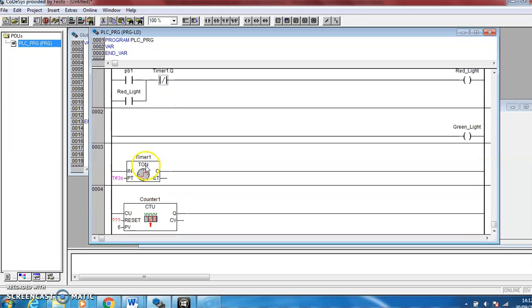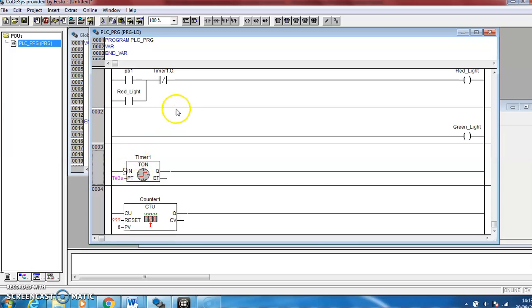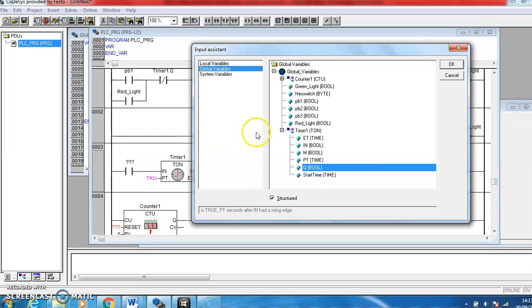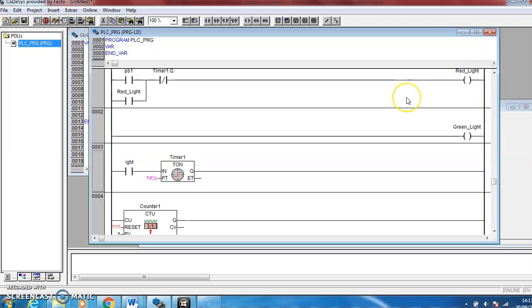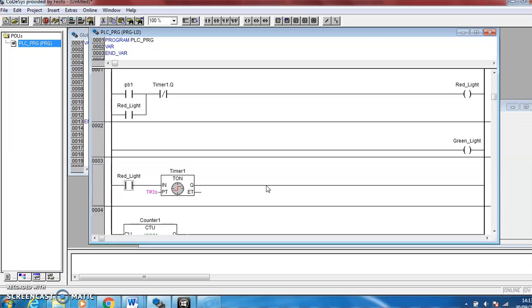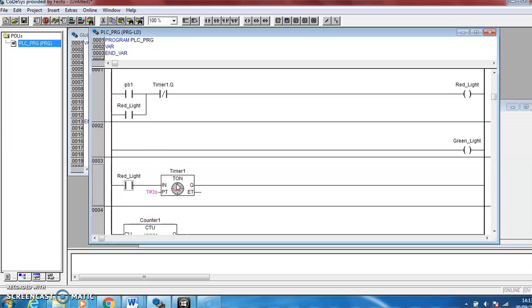So this TON style timer, this on delay timer, needs a constant signal to time but it also needs that constant signal to break at some stage so that it'll start to time again. So what we're going to do is use a normally open contact from the red light to control when the timer starts. So basically if the red light's off, the timer won't count. As soon as the red light goes on, this contact will close, the timer will start to count. After three seconds this output Q value from the timer will come on, this will open this contact, the red light will go off, both these contacts will open, the timer will stop counting, and it won't start again until the push button is pressed. So that's the red light sorted.